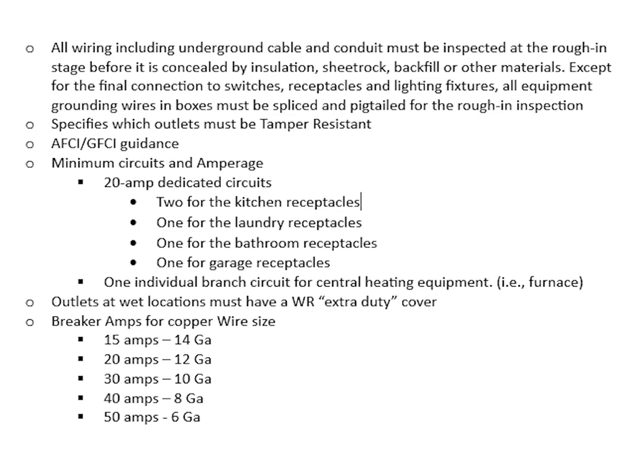Here's a table for copper wire size based on breaker amperage. 15 amp breakers require 14 gauge wire, 20 amp breaker, 12 gauge wire, 30 amp breaker, 10 gauge wire, 40 amp breaker, 8 gauge wire, and 50 amp breaker, 6 gauge wire.